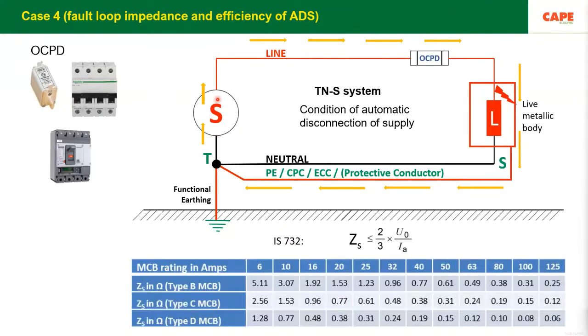In the upcoming National Electrical Code, we have included this table which says, for every MCB, you can see MCBs are of type B, type C, type D, depending upon the type of the MCB and its rating, the maximum allowed fault loop impedances are included in a table.